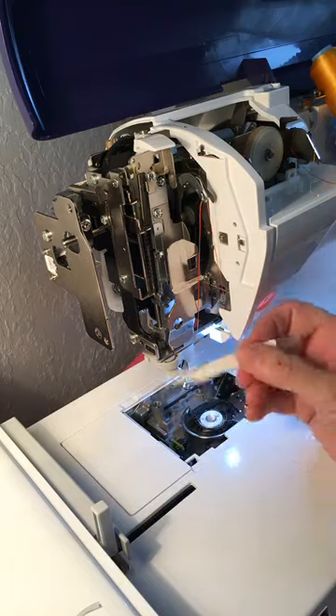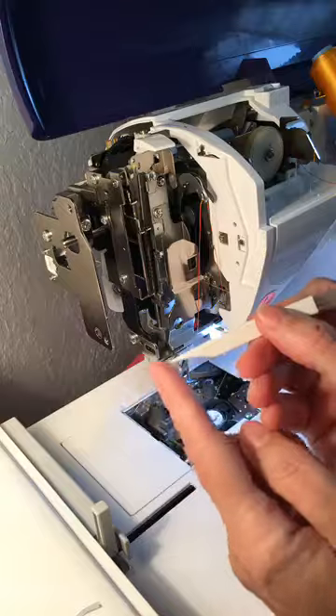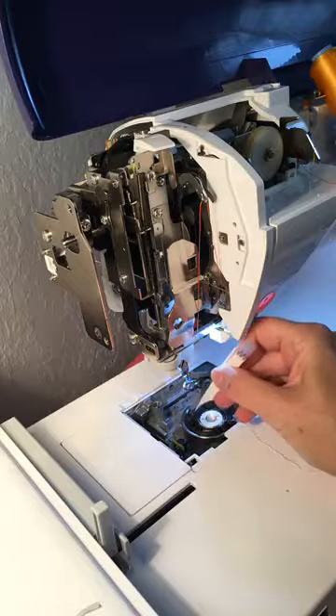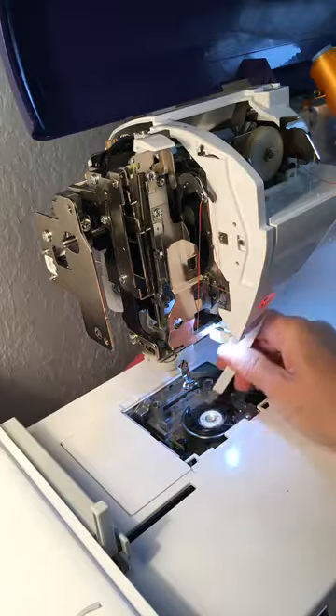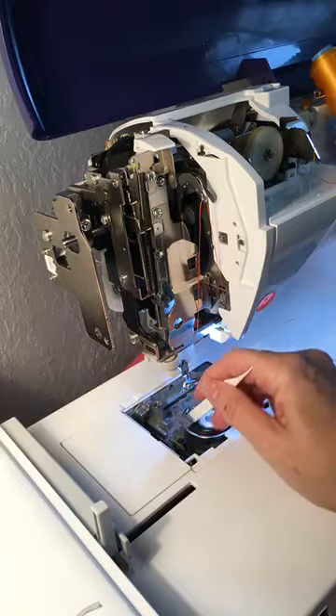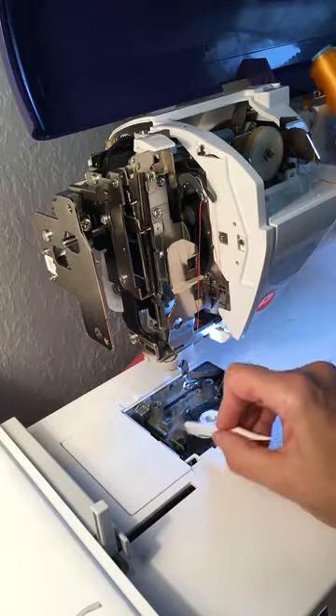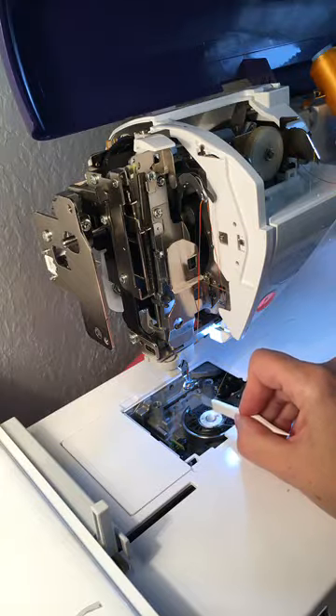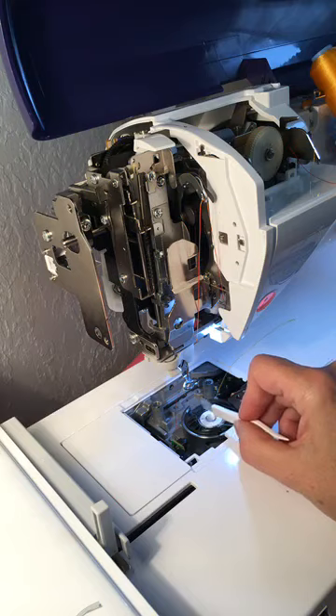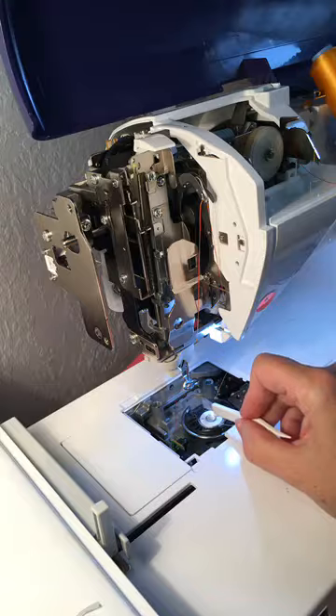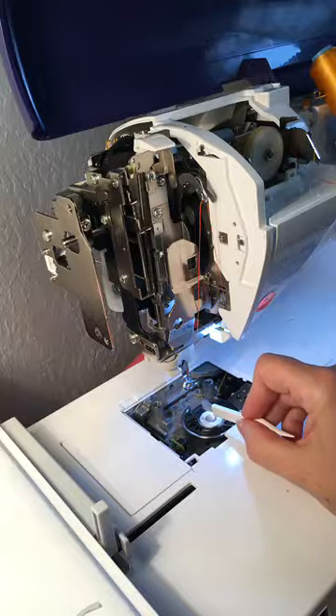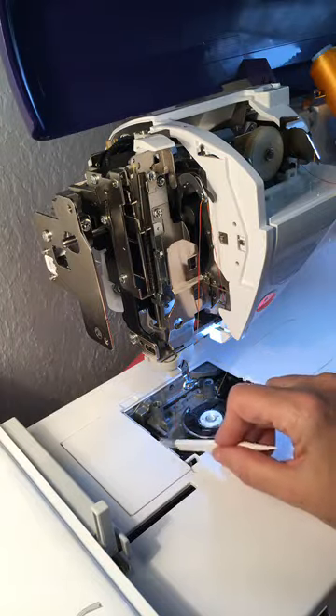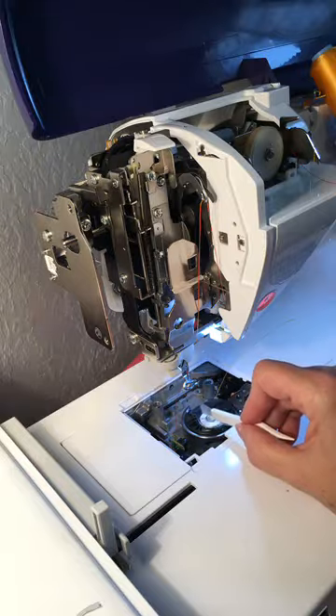I usually take this little brush, this sharp pointed end, and I just kind of run it along that brush just like that to clean that out. You can use the soft bristle end as well, but you want to keep that cutter clean. A lot of times the cutter will get stuck out. It'll come out and just get hung, and so it's such a fragile part of the machine that it'll just freeze. It's sort of like your garage door opener. If you are trying to go in and out of your garage door while it's going up or down, what happens to most of them? Most of them now have such a safety feature that it will stop as soon as something crosses the beam to avoid hurting someone. And so that's what happens to your cutter. It comes out and gets caught on something, so it just freezes right where it is.